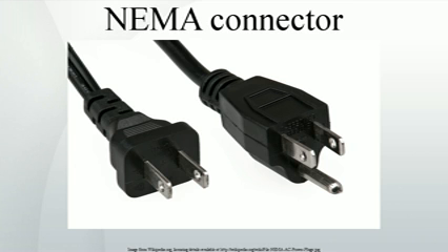NEMA nomenclature. There are two basic classifications of NEMA device, straight blade and locking. The straight blade 5-15 and 5-20 are found nearly everywhere in countries using the NEMA standards, and are intended for supplying lighter-duty, general-purpose electrical devices. Twist-locking types are used for heavy industrial and commercial equipment, where increased protection against accidental disconnection is required. Numbers prefixed by L are curved blade, twist-locking connectors. Others are straight blade and non-locking. The metal conductive blades are sometimes informally called prongs, as in three-prong plug.